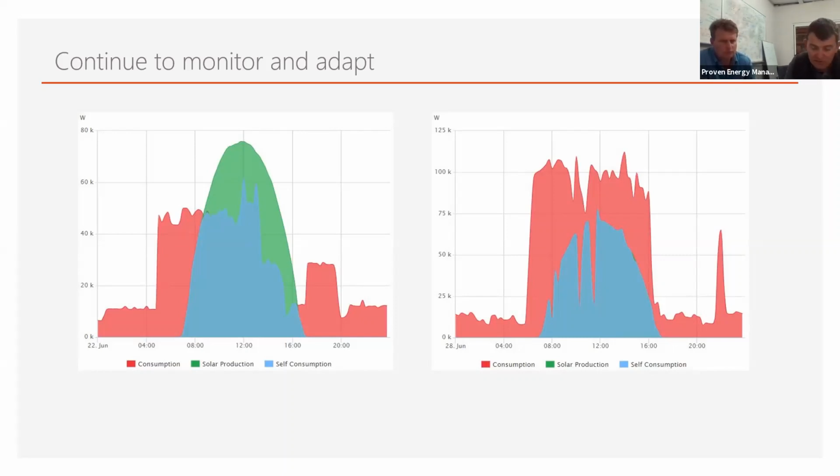For example, you mentioned earlier with systems over 30 kilowatts, there is some more expense, and that comes in the form of application fees to the network. And that can be $5,000 to $10,000 of basically, you know, dead money that's not buying plant and equipment each time we go back to the network to do an expansion. So where we can, we want to size for the foreseeable future. But when we're talking about large systems like this one, which will be 250 kilowatts when we're done, I guess that expense is amortized over the whole size of the project anyway.